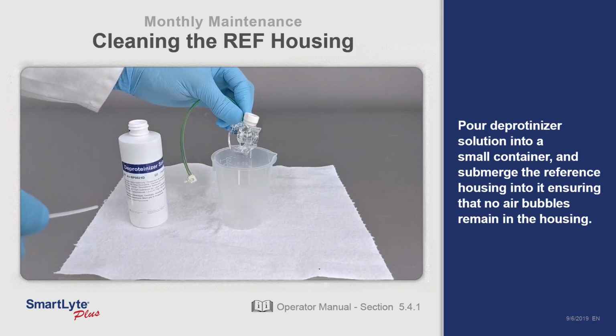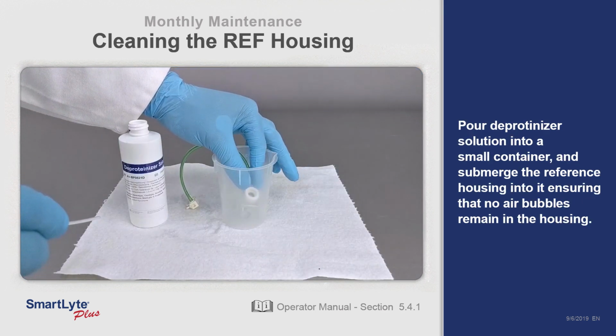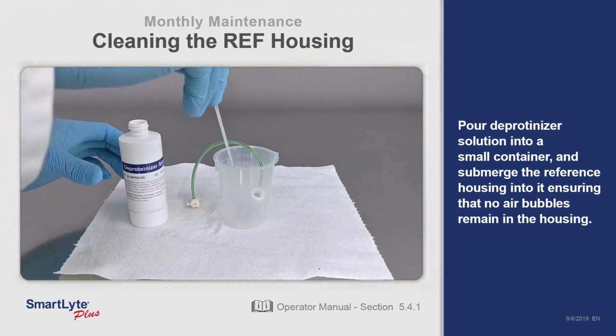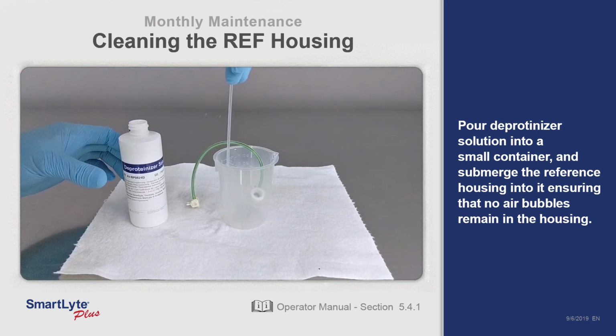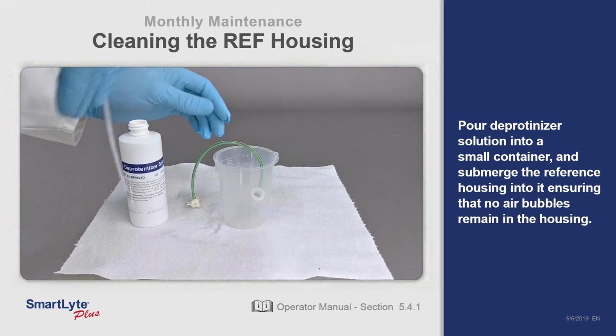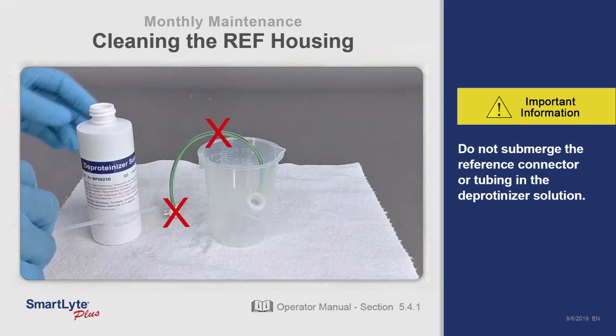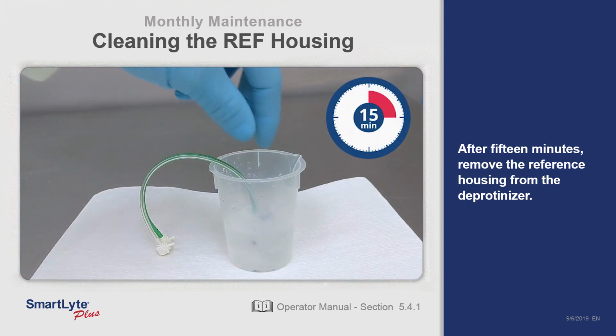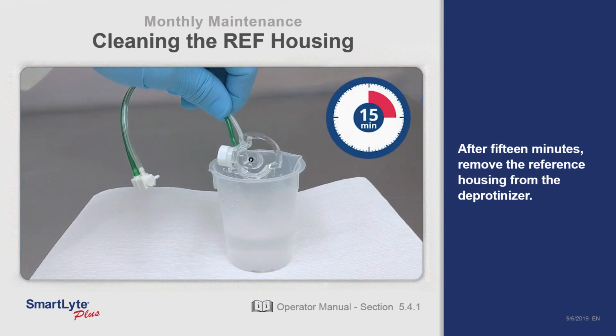Pour deprotonizer solution into a small container and submerge the reference housing into it, ensuring that no air bubbles remain in the housing. Do not submerge the reference connector or tubing in the deprotonizer solution. After 15 minutes, remove the reference housing from the deprotonizer.